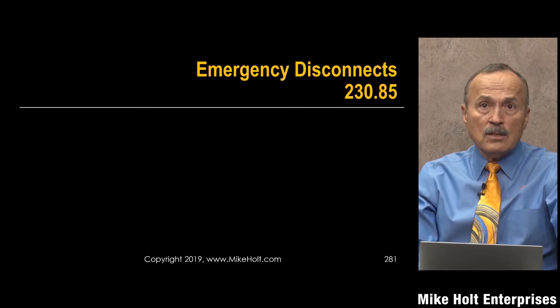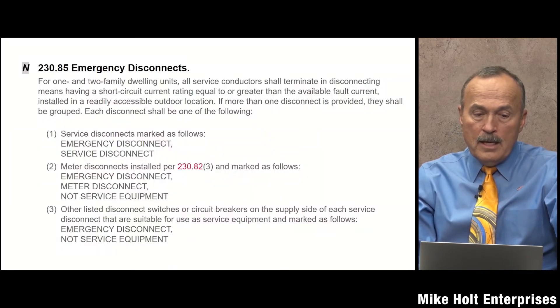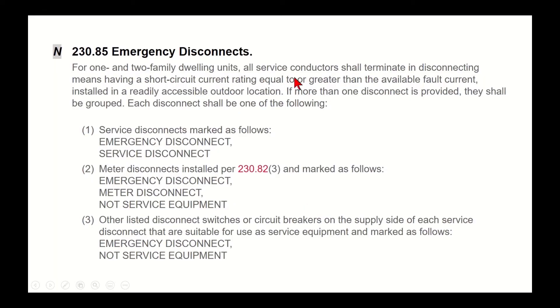Now we're into the emergency disconnect in 230.85. For one or two family dwellings, all service conductors shall terminate in a disconnecting means having a short-circuit current rating equal to or greater than the available fault current — that's 110.10 — installed in a readily accessible location.